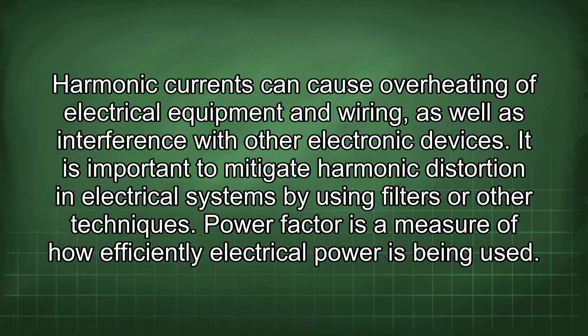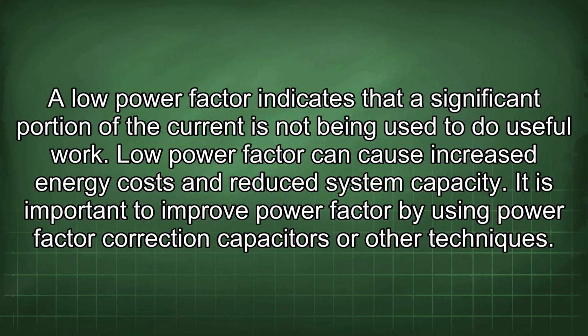Power factor is a measure of how efficiently electrical power is being used. A low power factor indicates that a significant portion of the current is not being used to do useful work. Low power factor can cause increased energy costs and reduce system capacity. It is important to improve power factor by using power factor correction capacitors or other techniques.